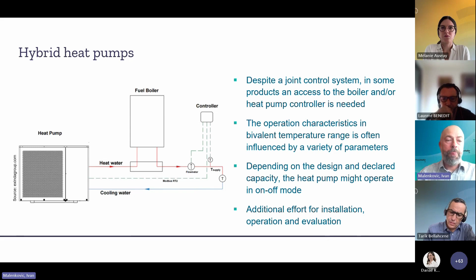Finally, a new test procedure is being developed. The rationale behind it is not to exclude the appliance's controls from the measurement, but to include them, to let the unit run with its own controls. What a test lab needs to do is impose a certain heating or cooling load on the appliance and control it by the test facility.